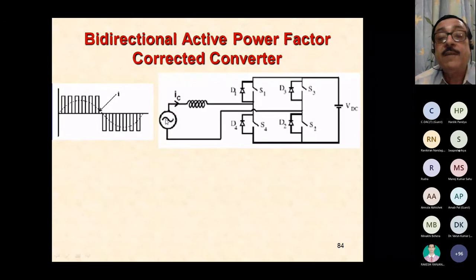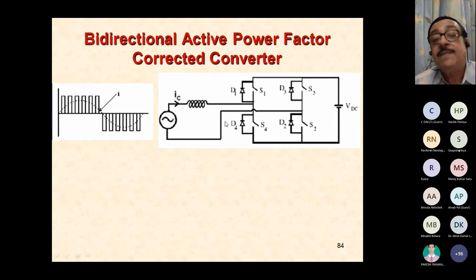If I'm sending power from the AC side to DC side, then this is my boost inductor for boosting up the voltage to match the required DC voltage from the AC side. And if I'm sending power from the DC side to AC side, this inductor is for limiting the circulating harmonic currents. Why? Because you'll realize this waveform is a pulse width modulated waveform, something like this.